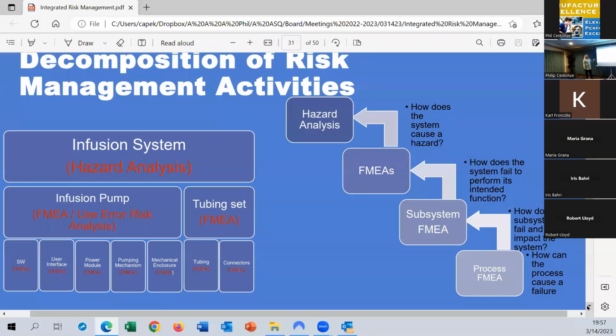But if they fail, I need to be able to keep my patients safe, right? So this might only fail 1 in a million times, but that one time it fails, I have to keep my patient safe at the system. And that's why hazards are mitigated at the system. Doing FMEA analysis will improve the reliability of the different components of the system so that you lower your P1, you lower the likelihood that this is going to fail.